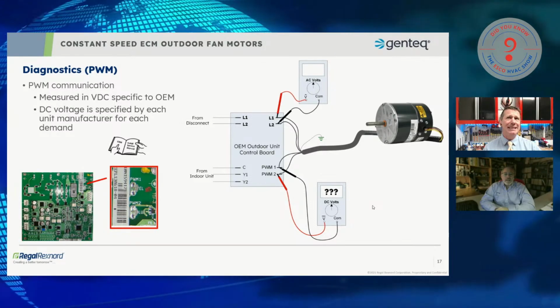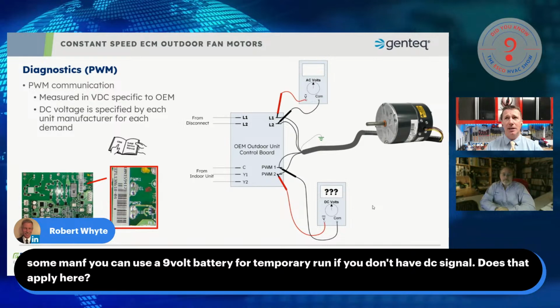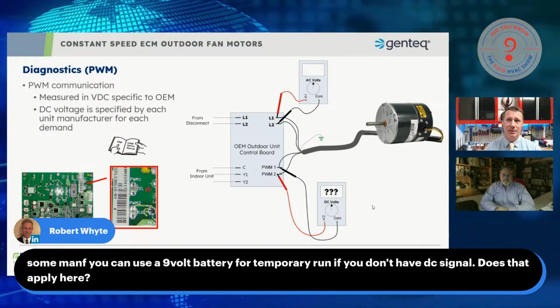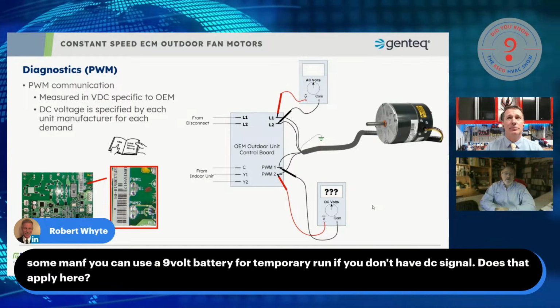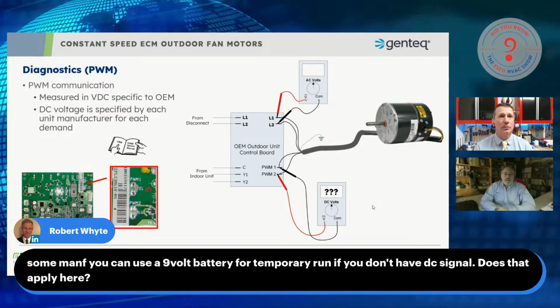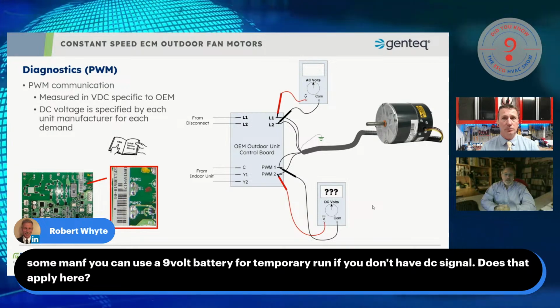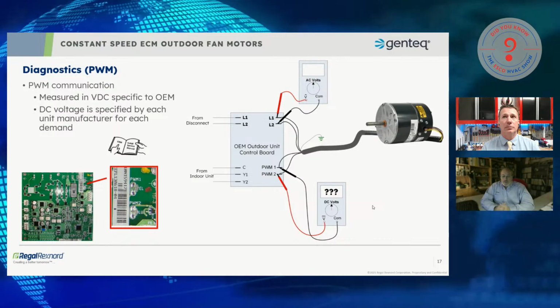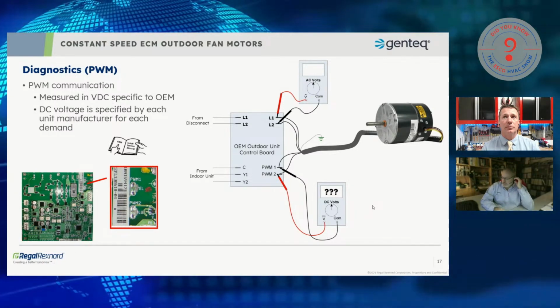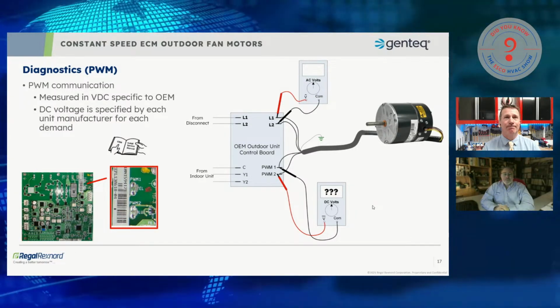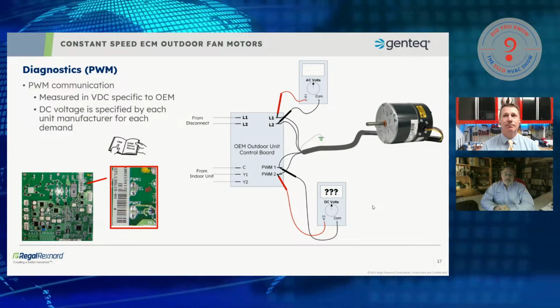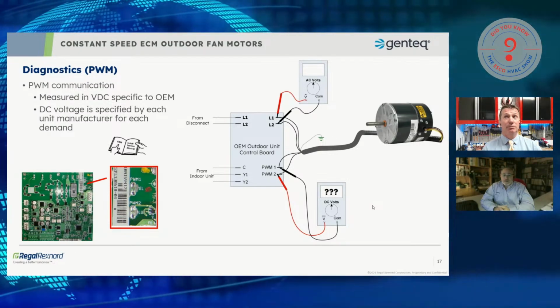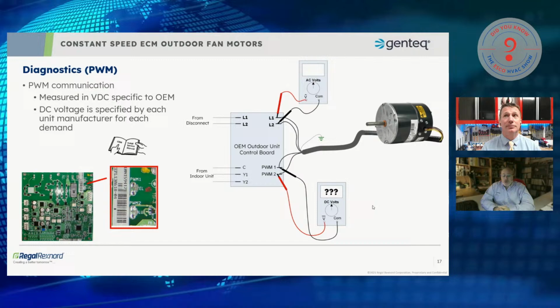Yeah, one probably needs to be addressed, or at least touched on a little bit, because we can all relate to the old days of ECMs. Yep. So I'll hit that one. The one from Robert White about some manufacturers say you can use a 9-volt battery to temporarily run a motor that has a DC signal. Does that apply here? That was a practice, and I won't call out the manufacturer for it, but that was a practice that one OEM recommended for diagnosing the constant airflow variable speed motors a long time ago.